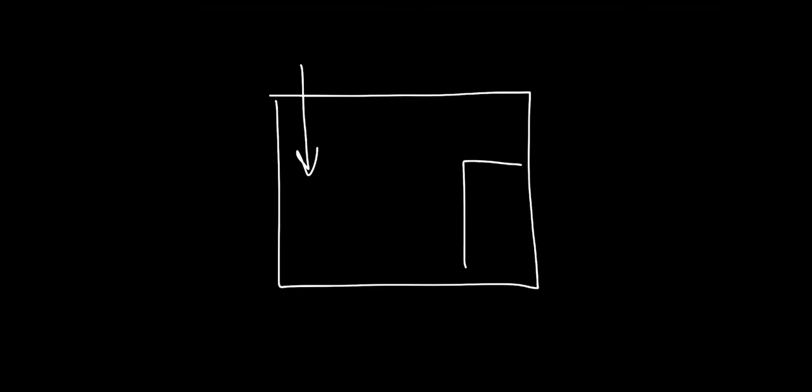In order to maintain a negative pressure relationship within the laboratory, we need to supply less airflow to the lab than is exhausted from the room. The volume of exhaust is based on the combined exhaust flow rates for the fume hoods utilized and the minimum required air changes per hour.